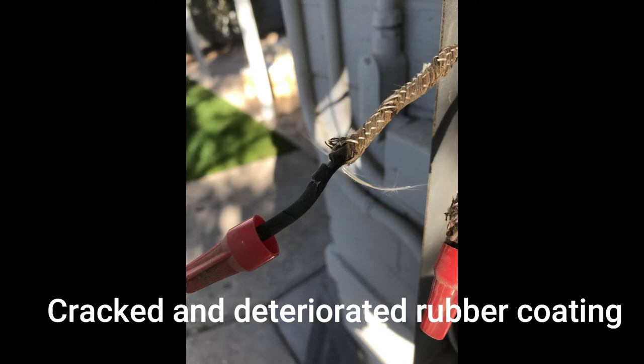The first and most important reason being that it was installed in the 60's and the rubber coating on the wire is almost always deteriorated and brittle. More times than not, it will crack and fall off leaving the bare wire exposed.